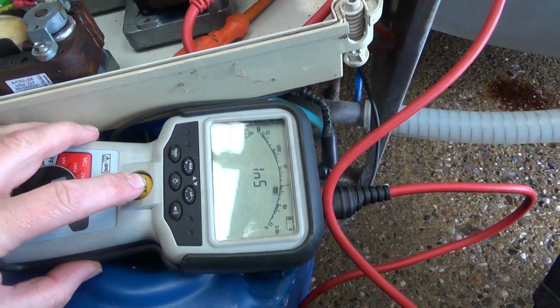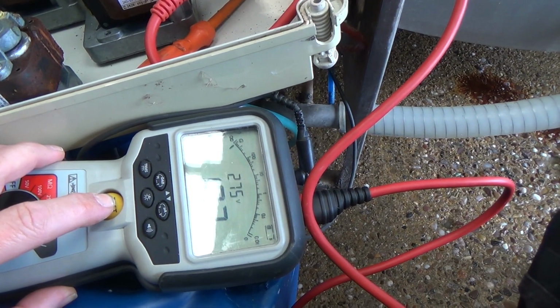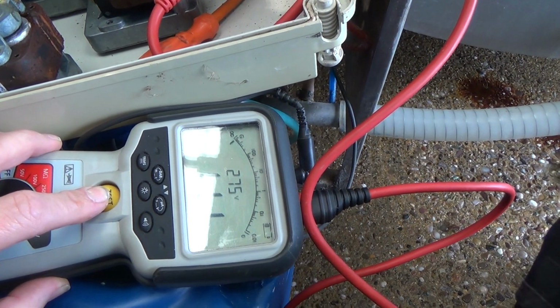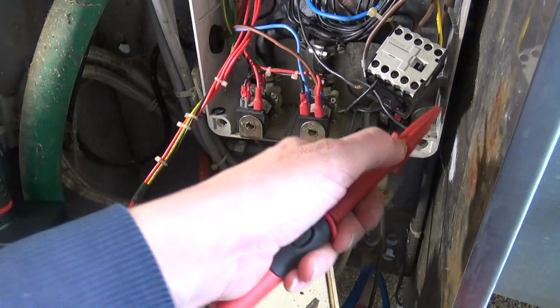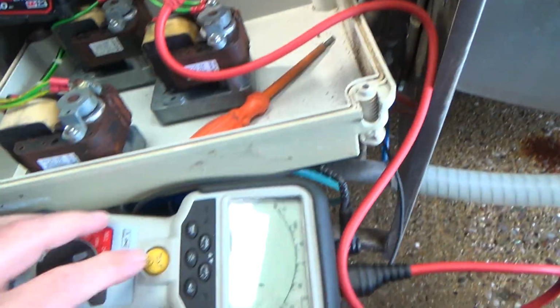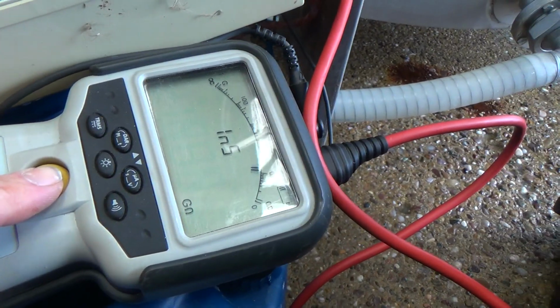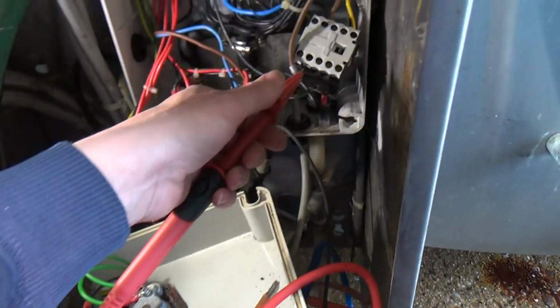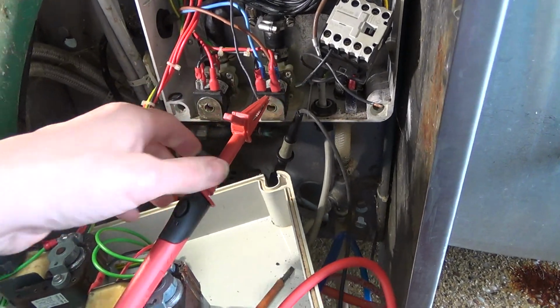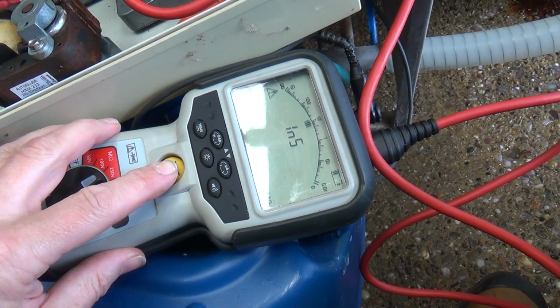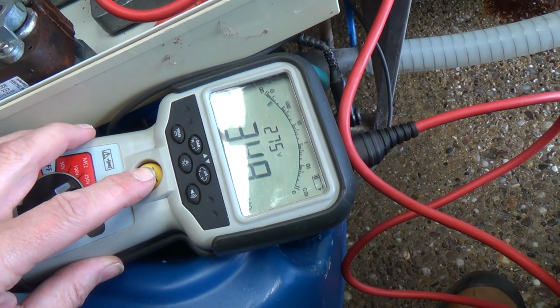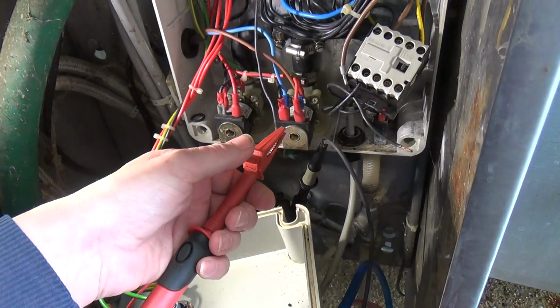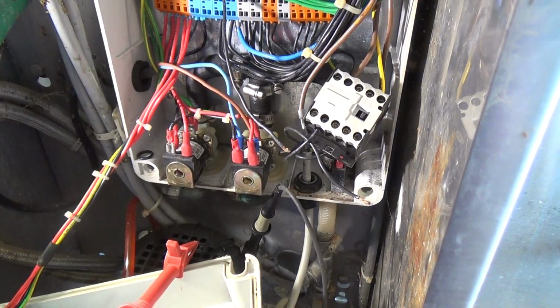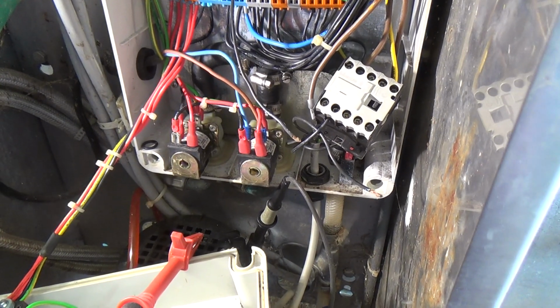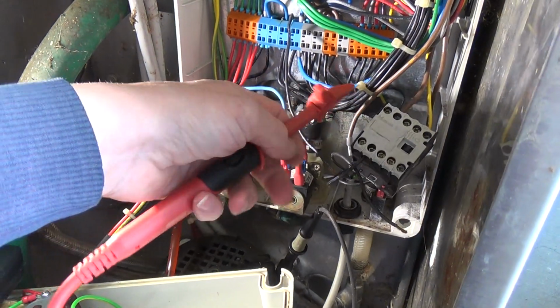So what do we got here? This is looking gigaohms, we're off the scale again, so let's confirm we've still got a short. We have. Oh well, so it doesn't look like it's the pump or the dump valve. Let's try that. This is the neutral on the bus bar. Megaohms. Ooh. And then what have we got on here?